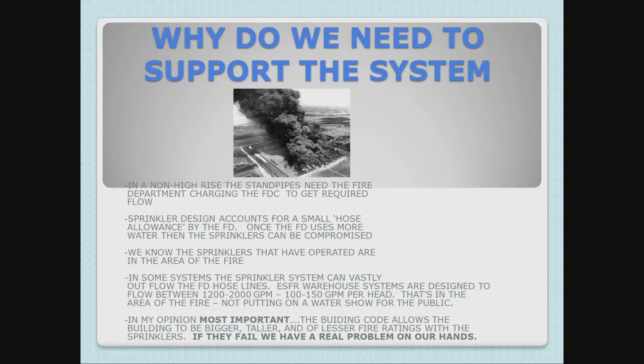But in a non-high-rise, the standpipes must be charged because the FDC is the only way you're going to get your flow. In a non-high-rise building, the flows inside the building are calculated to just the sprinkler flow. You will not get the required standpipe flow until you pump into that connection. Now, in a high-rise building, that's different. A high-rise building is designed to give you the flows, which is 500 gallons a minute for the most remote standpipe and 250 gallons per minute for each additional standpipe. High-rises are designed to give you that all day long on their own without us ever even pumping into the FDC. That's what they're designed to do.